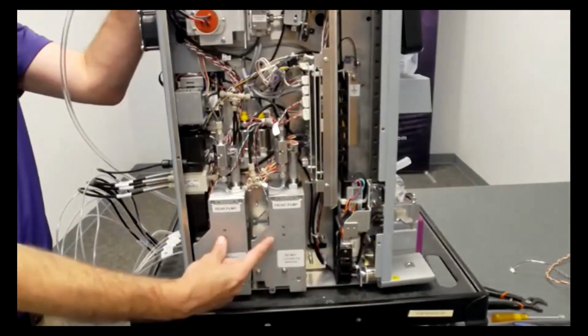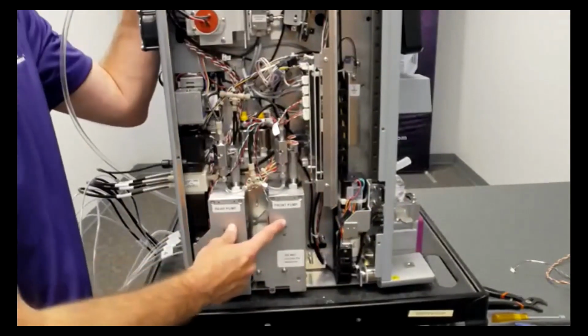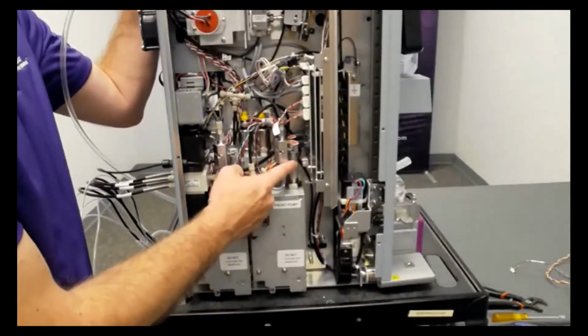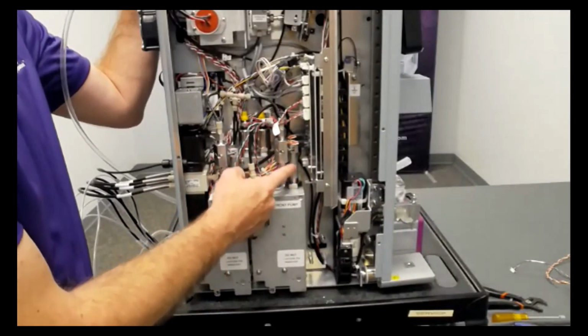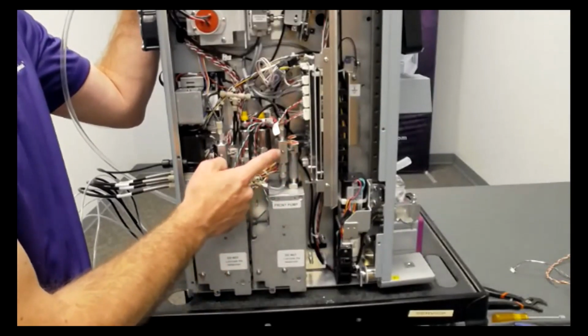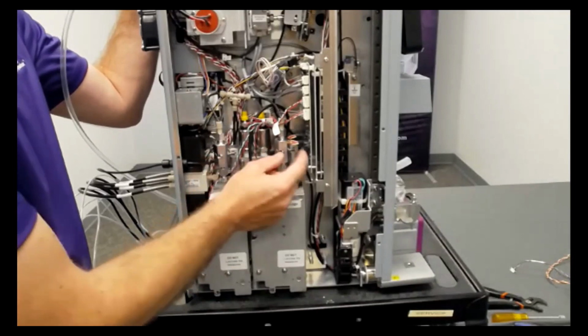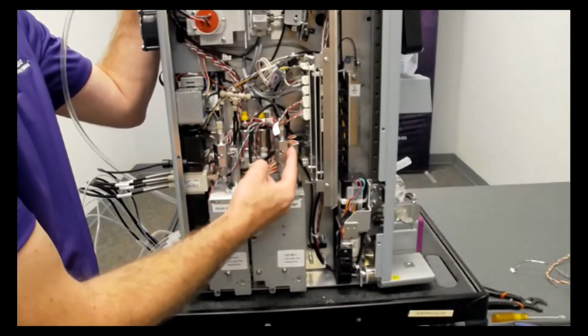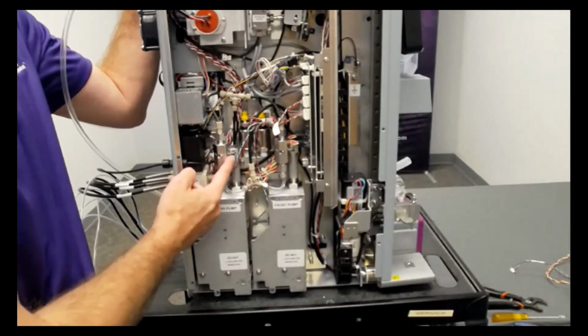Here are the pumps, okay? So on the pumps right here is the cylinder that I was talking about. This is where the seal is. And here's the check valve housing. So the O-ring that you replace is in between here. And on this one, it's right here.